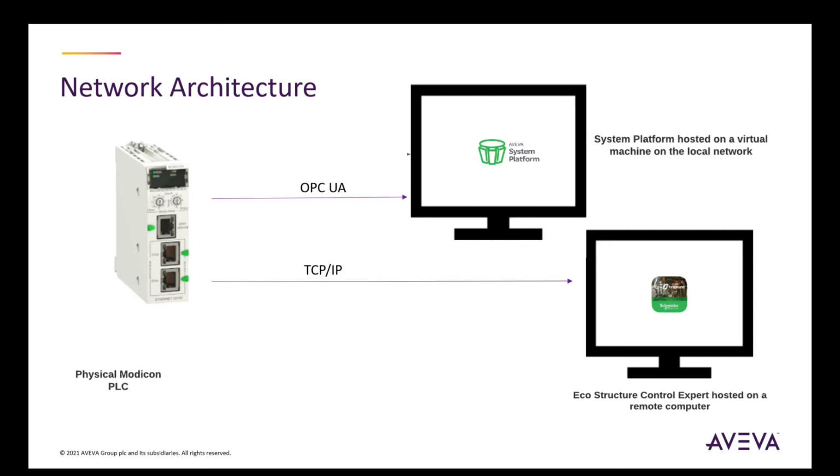Control Expert is used to configure and program the PLC, which is connected to the network via Ethernet using TCP/IP protocol. Control Expert will only be used during the engineering stage of this process. The data communication protocol that is used to read and write data to the PLC from System Platform is OPC UA through the Modicon communication server.